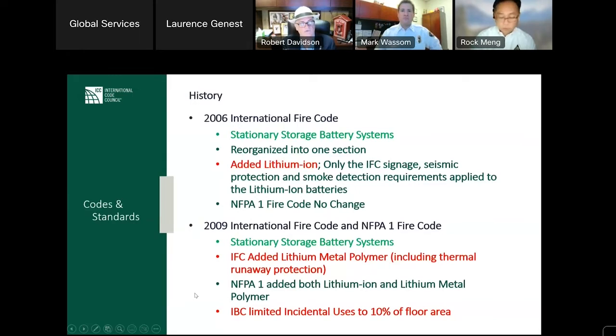This is important for you to remember, because if you're on an older edition of the code that didn't catch up with energy storage system requirements, it didn't recognize the hazard, and what's in there is not adequate. We only required seismic and smoke detection requirements. And NFPA 1 didn't make a code change at that time. We didn't always remember to address both fire codes in the same cycle.